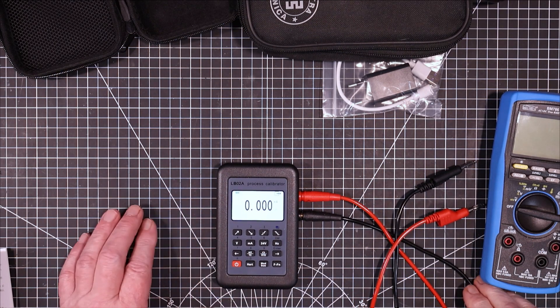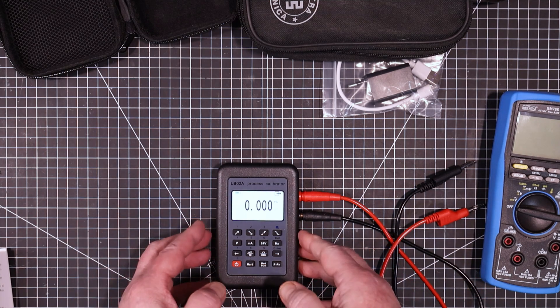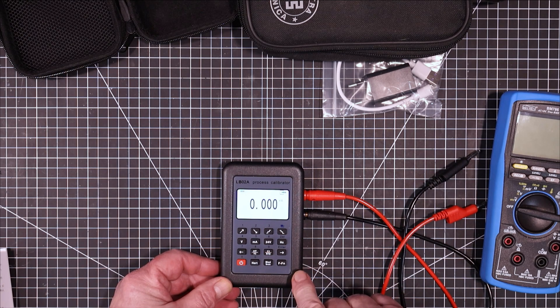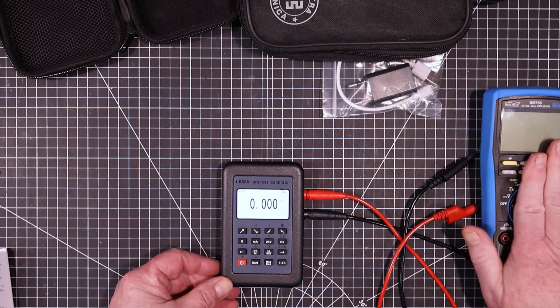So that is the LB02A process calibrator. I think it's going to come in very handy when I have to test multimeters here on the bench. I'm going to be using this in the future. Because we've seen how accurate it is. With this four and a half digit meter here. It's a very accurate meter.